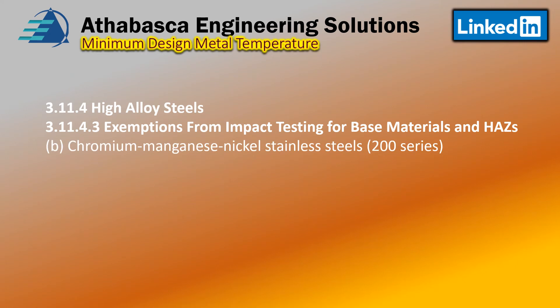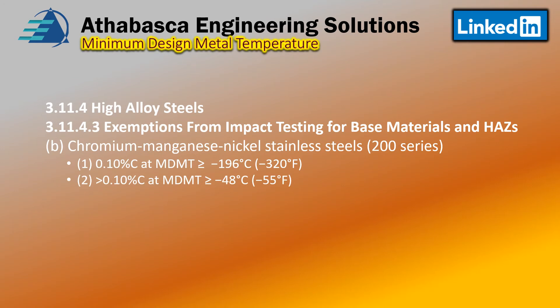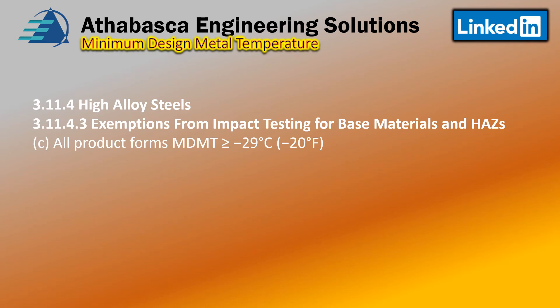For chromium-manganese-nickel stainless steels, the 200 series, if carbon content is no more than 0.1% and the MDMT is greater than minus 196°C, you are exempt. If carbon content is greater than 0.1%, the MDMT exemption is only to minus 48°C — very similar to the other materials. For castings, it's set to minus 29°C. For all product forms, there is an exemption if the MDMT is equal to or greater than minus 29°C.